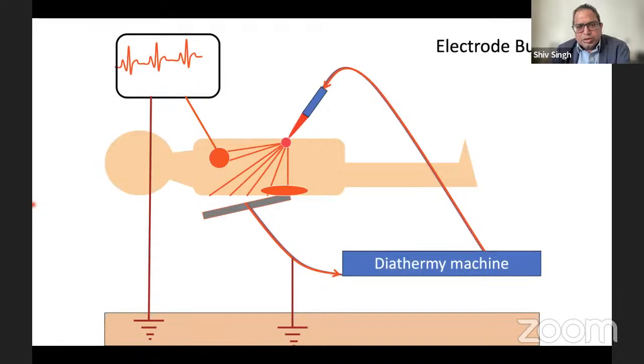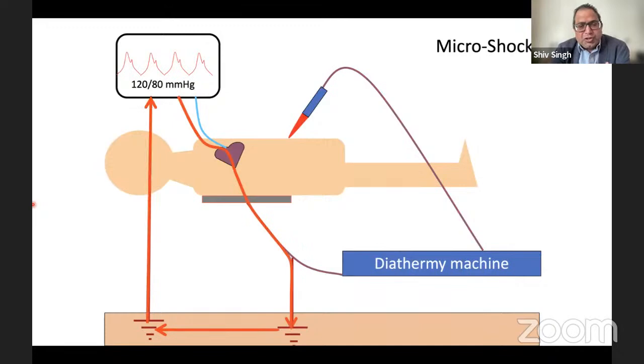So how can we prevent that? The next level of diathermy. Microshock is also common when there is earth. If you have equipment or a monitoring system which is earthed, and there's a leakage of current, then it can complete the circuit through the earth plate. So it becomes a risk for microshock as well. Not only burns, but also the risk of microshock increases in a patient with an earthed diathermy.